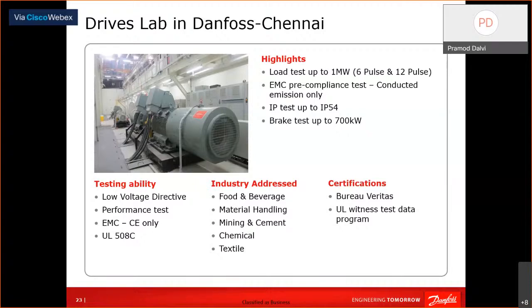We also have an EMC test. This is an upcoming topic now, since the VFD is a switching device that generates harmonics, which can cause malfunction in other sensitive equipment. In those areas, EMC testing or type testing is becoming mandatory, and we have our own setup for that.